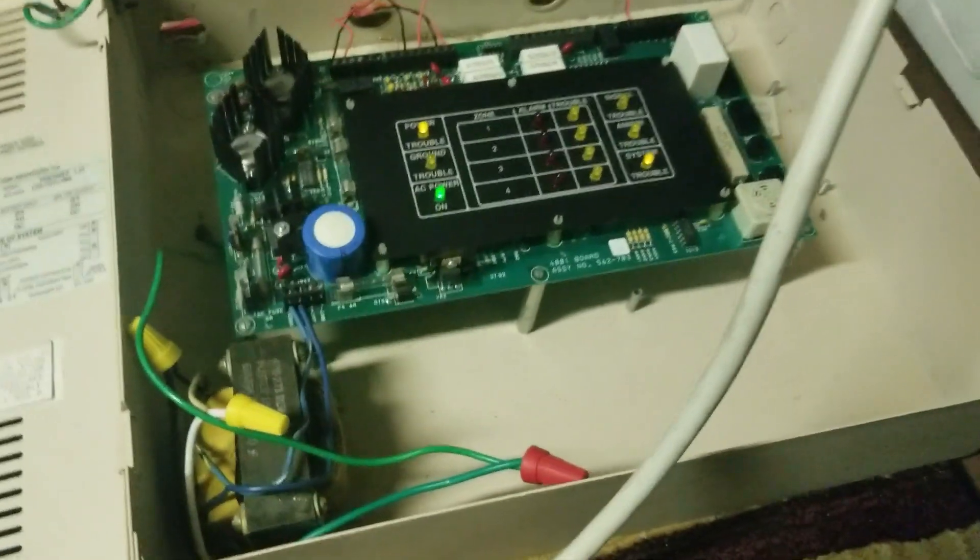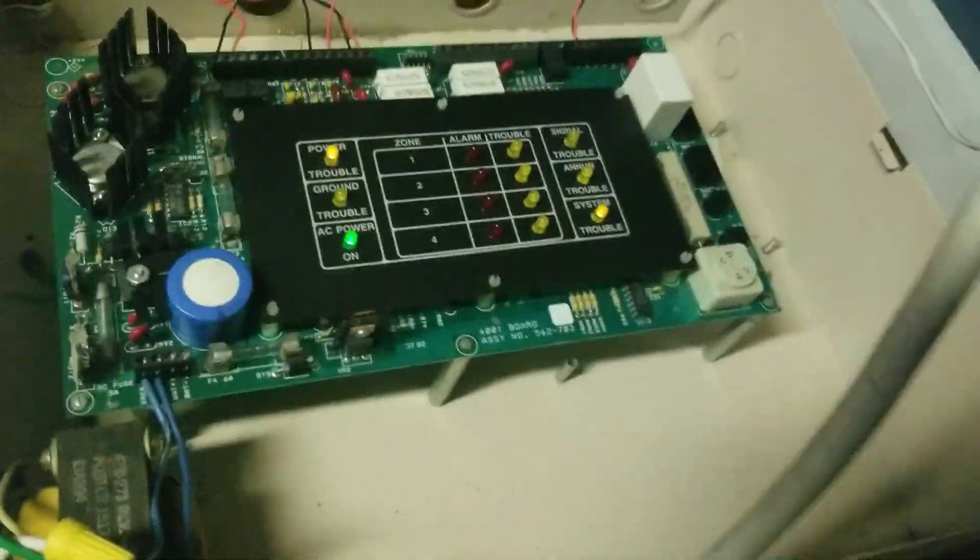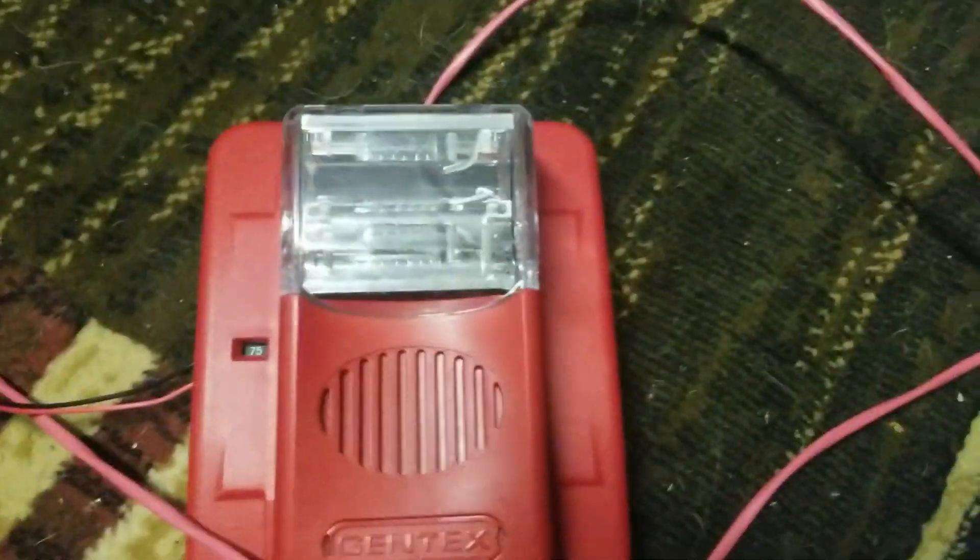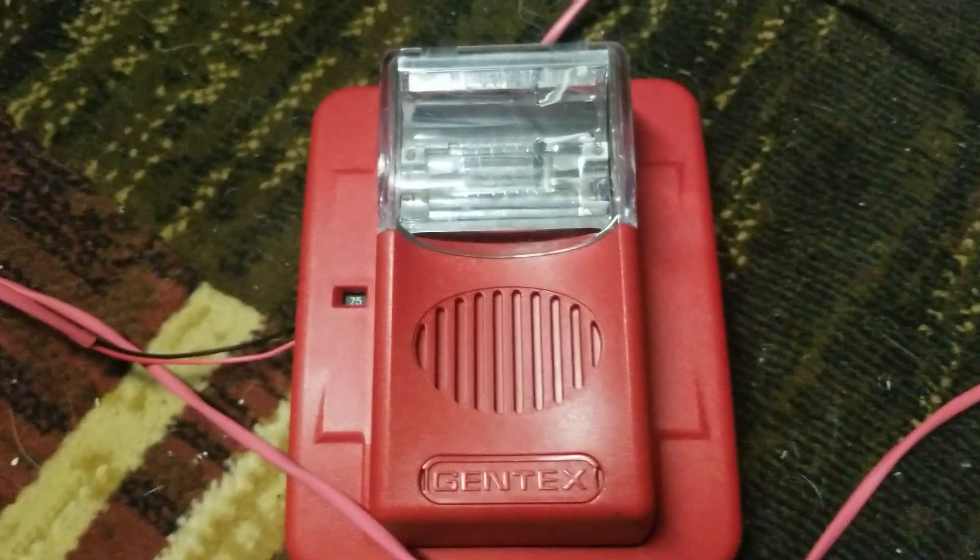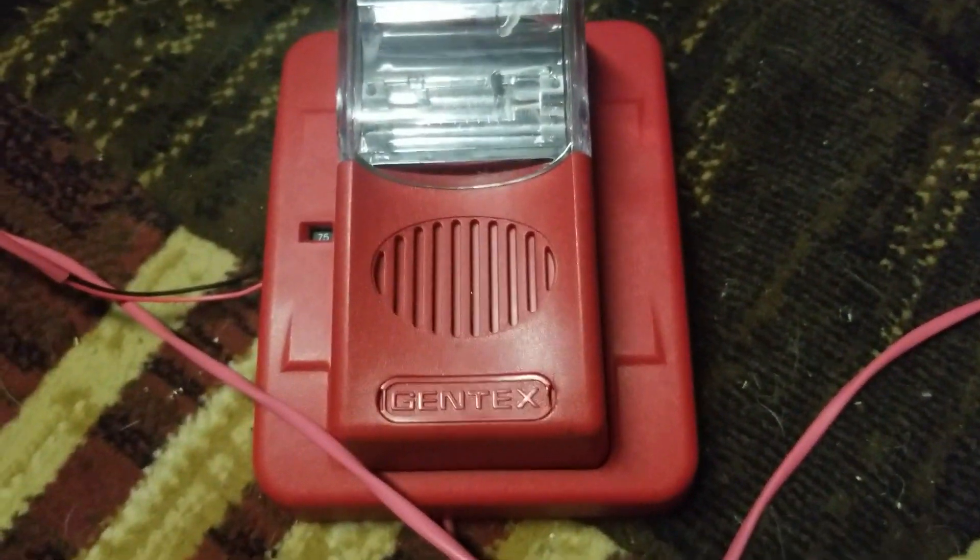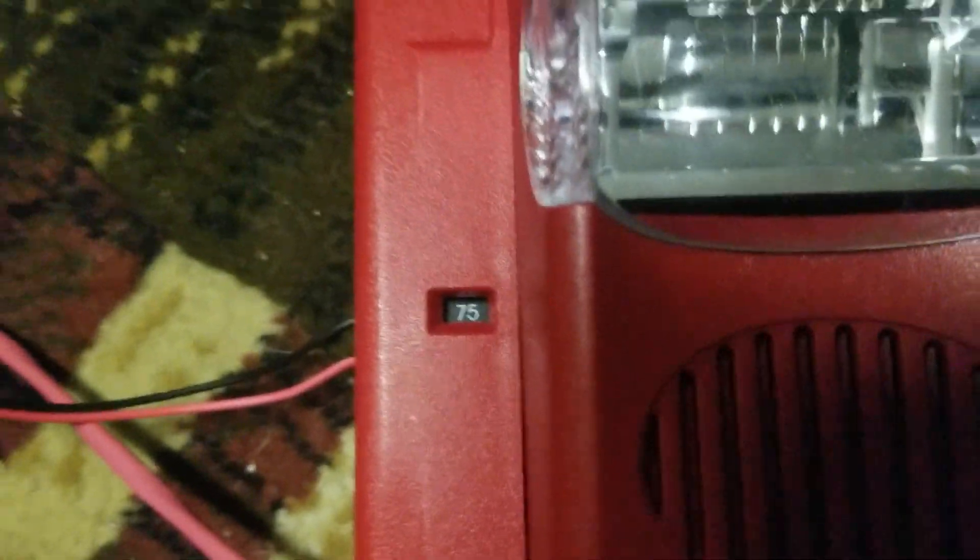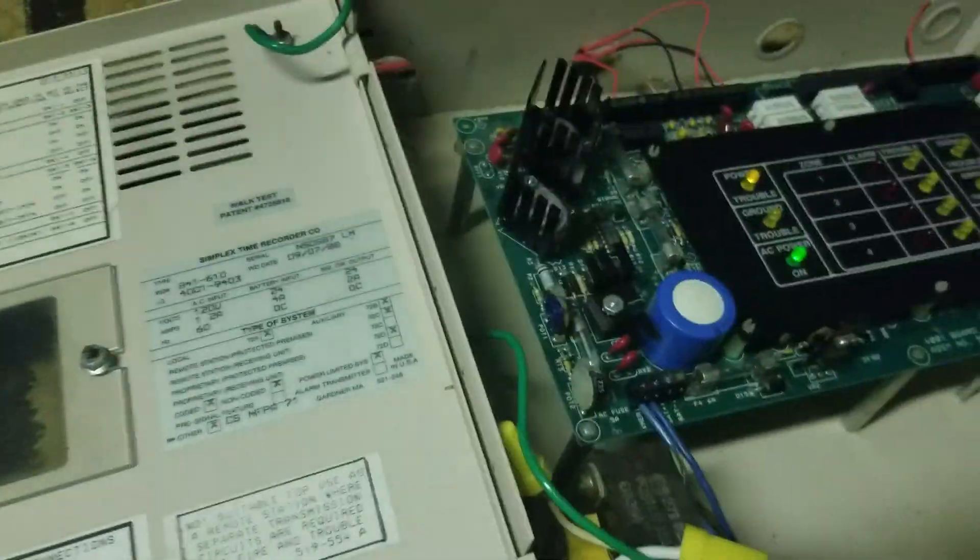So what devices do we have in the system? First, I have my Gentex Commander 3 which is set to the high frequency tone at 75 candela and continuous as well because it'll be coded by the panel.